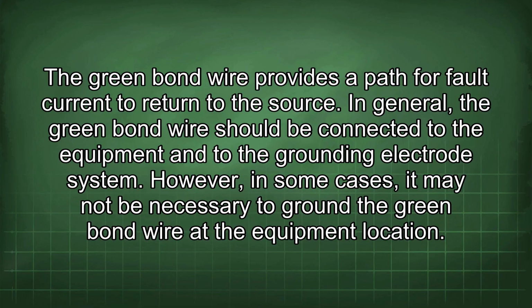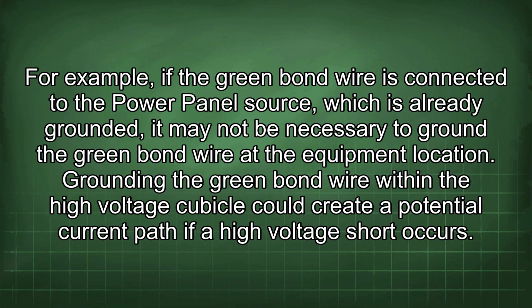In general, the green bond wire should be connected to the equipment and to the grounding electrode system. However, in some cases it may not be necessary to ground the green bond wire at the equipment location. For example, if the green bond wire is connected to the power panel source, which is already grounded, it may not be necessary to ground the green bond wire at the equipment location.